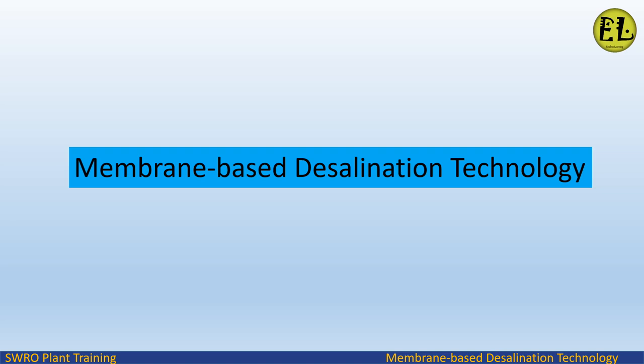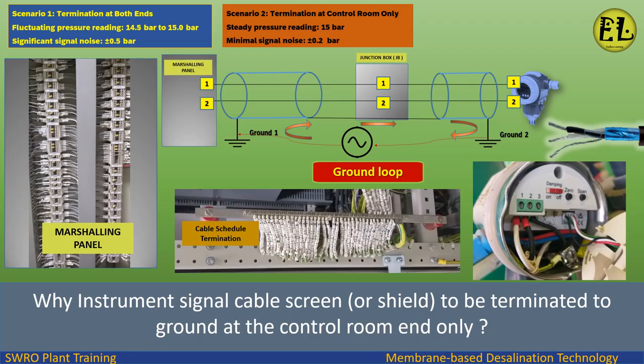Welcome to Endless Learning Training Series: The Membrane Based Desalination Technology. In this presentation we will study about why instrument signal cable screen or shield should be terminated to ground at the control room end only, and the screen should be left floating at the field instrument end, to avoid ground current loops.